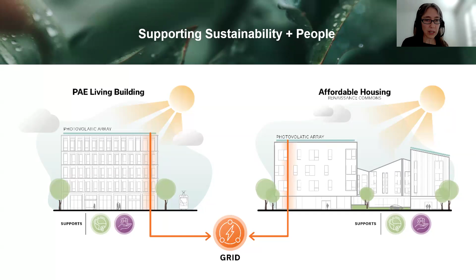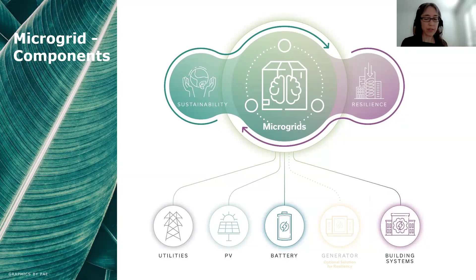To handle this, we installed a microgrid, which is effectively a fancy controller that handles the generation sources and loads. We also installed a battery system that helps us harness the additional PV production, storing it into the battery when we can't feed more back to the grid, and then feeding that back at a later time. It also gives some resilience so that we can island the building and keep things running even if the grid were to go out or there's some sort of local emergency.